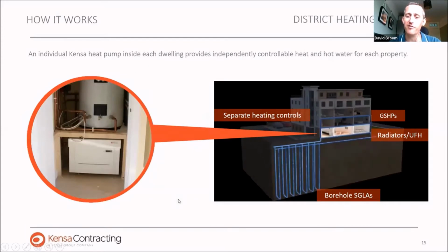Within the ground array, there you go. Within the ground source setup, where we have multiple heat pumps linked to a communal ground array, even the circulating pump that pushes the fluid through the boreholes is individual to each individual heat pump. So there's no central plant, there's no central pump pushing the fluid around the circuit.